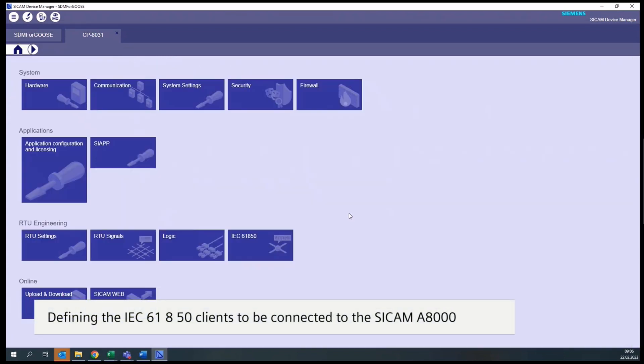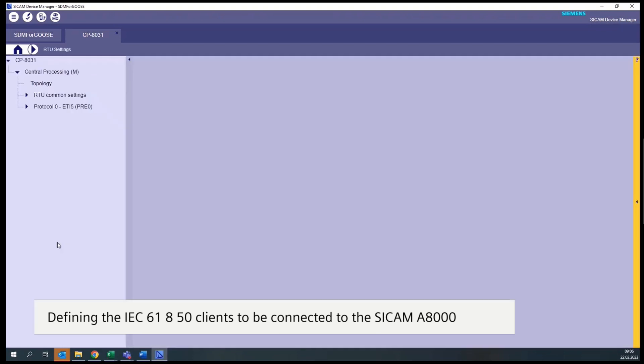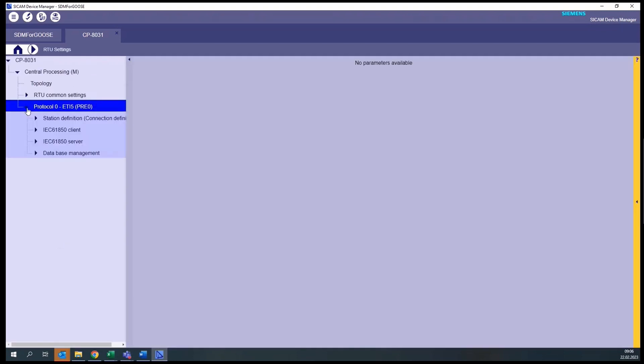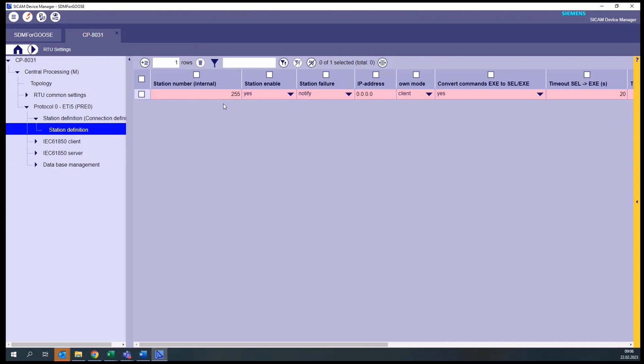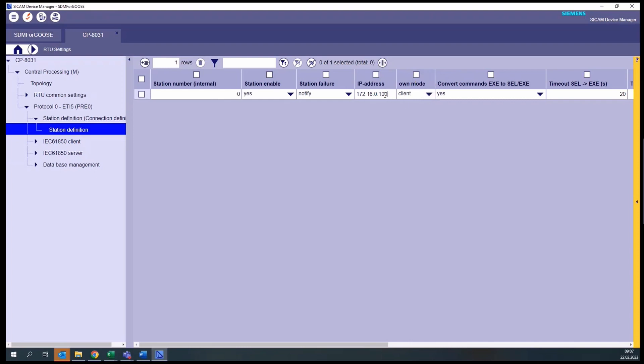We have to create an RTU Settings station for each IEC 61850 client that will subscribe to the SICAM A8000. For this example, let's assume we will have only one client. We assign the internal number designation for this station in the configuration — in this case, station 0. We must also define the IP address of this IEC 61850 client. We also need to define here the own mode of the SICAM A8000 for this connection.